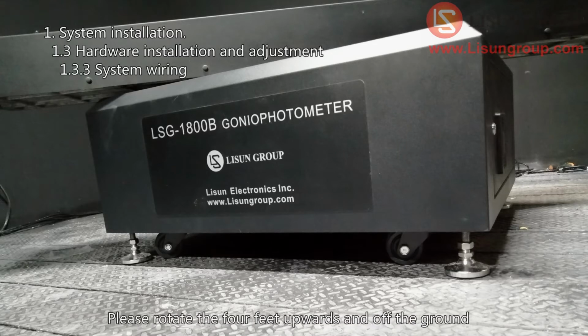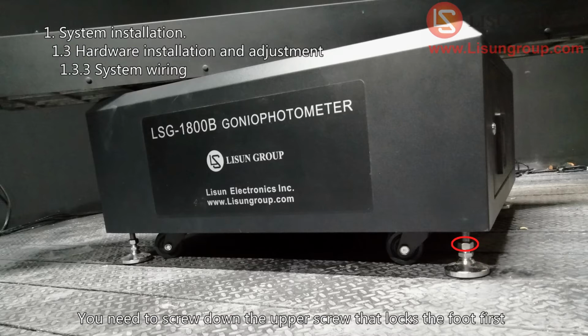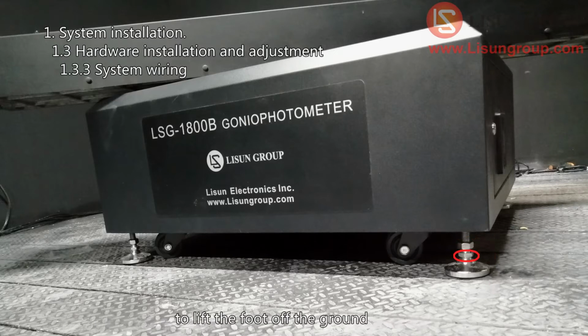Please rotate the 4 feet upwards and off the ground. Please note that there are 2 screws on each foot. You need to screw down the upper screw that locks the foot first, leaving enough space to turn the bottom screw upward to lift the foot off the ground. Then you can easily move the goniophotometer.